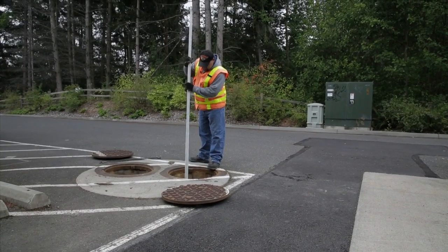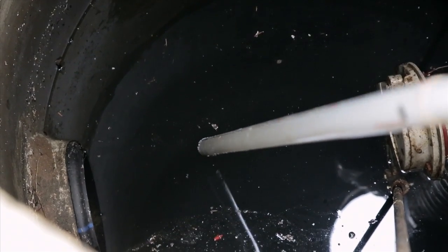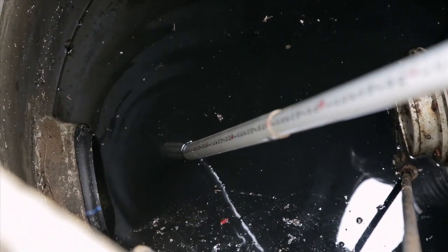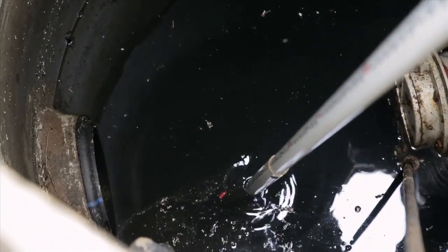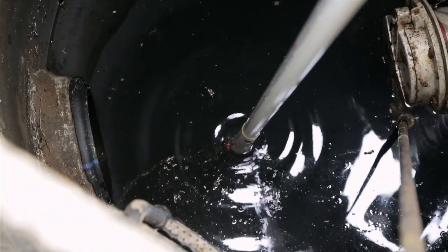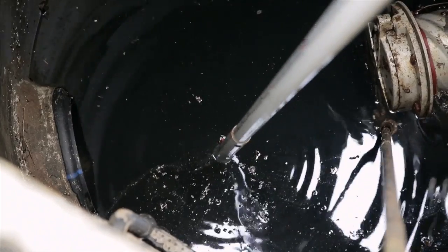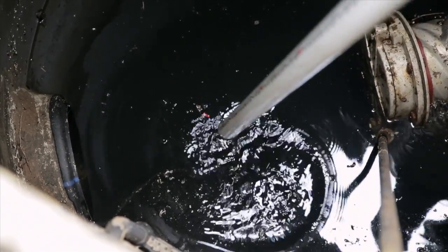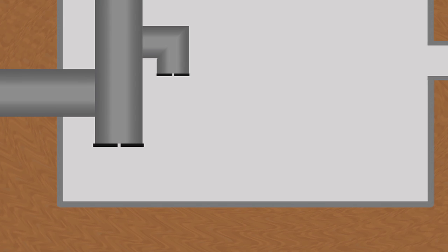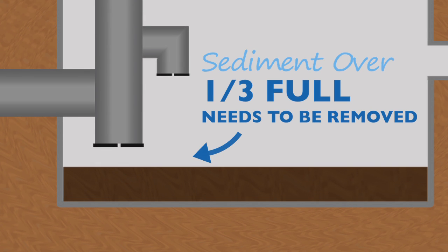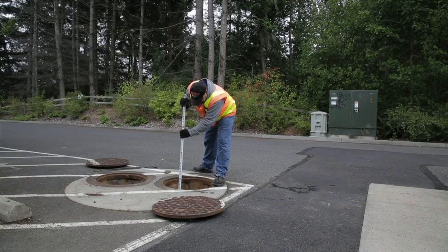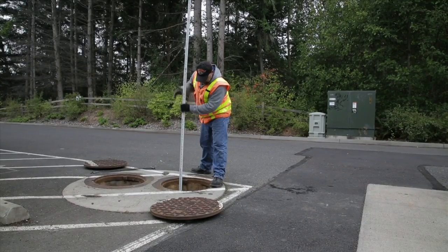To check for sediment buildup, take a pole or pipe and lower it through the water until you feel the top of the sediment. Then push it to the bottom of the structure. This will give you an idea of how much sediment has accumulated. If the sediment is more than 1/3 the depth from the bottom of the basin to the lowest pipe, it should be removed by professionals. Hire a licensed contractor with a vacuum truck to remove and properly dispose of the sediment and debris. If the sediment accumulation does not cover the bottom third of the structure, it does not require removal, but should be checked regularly.